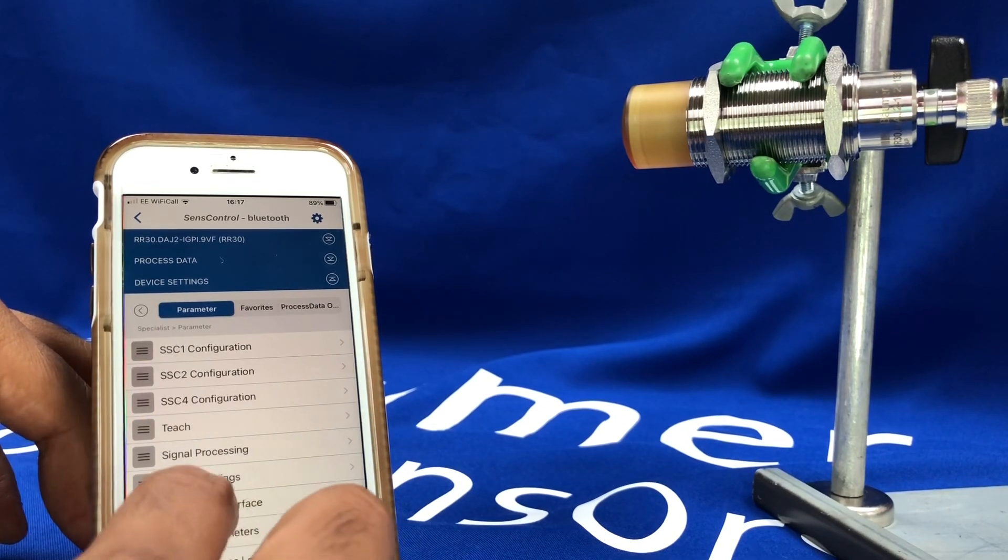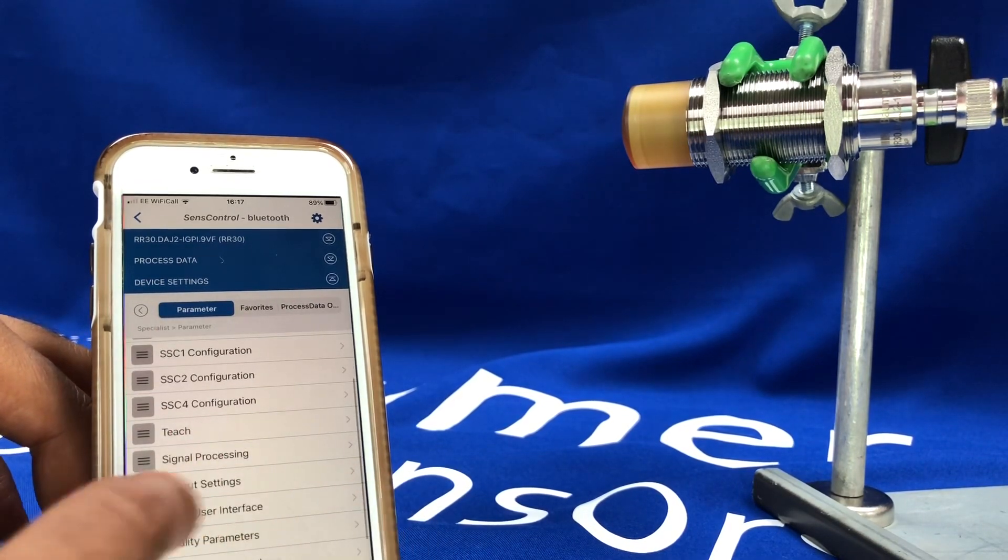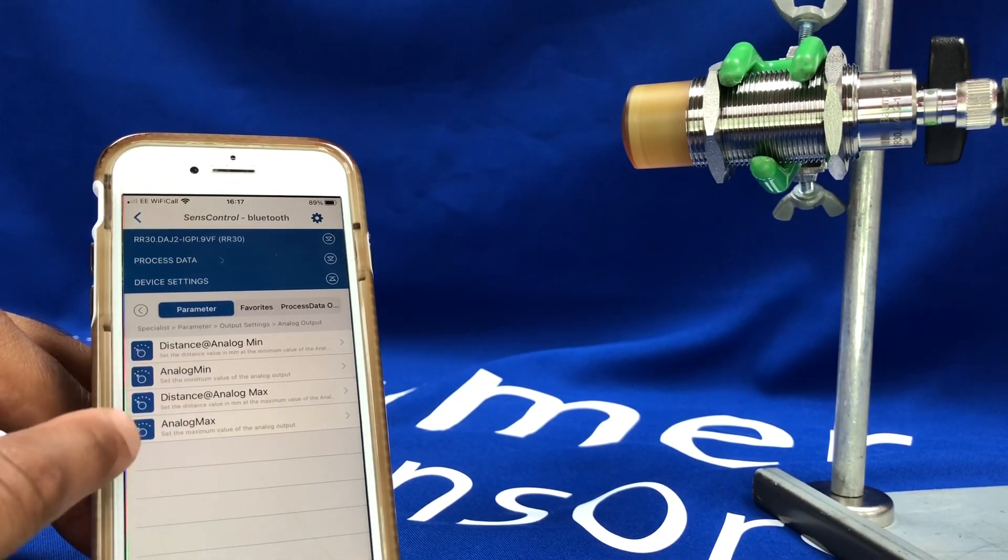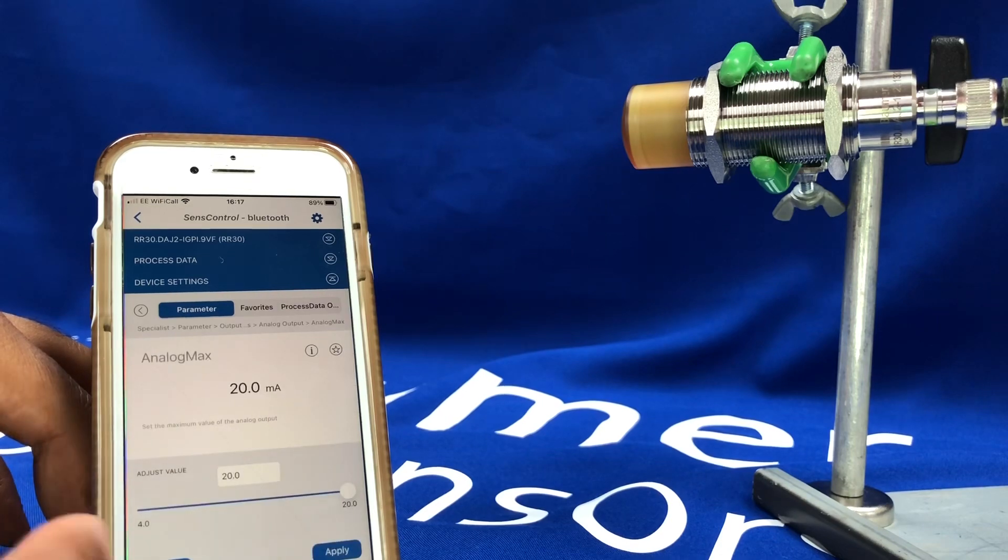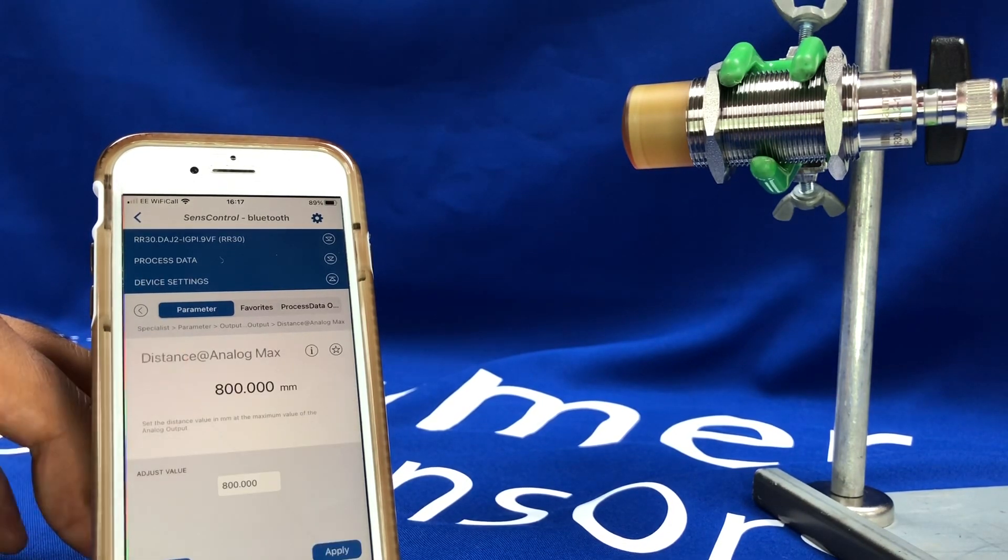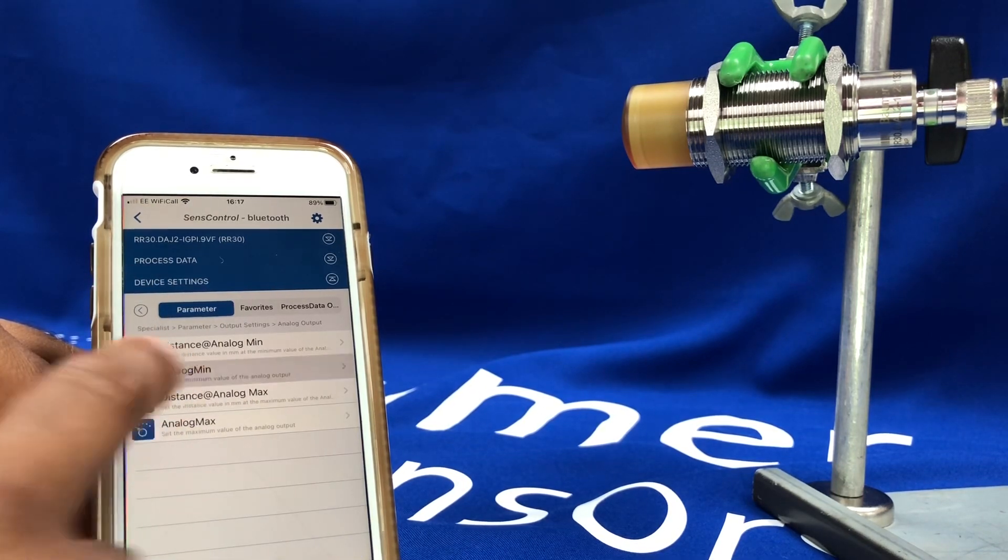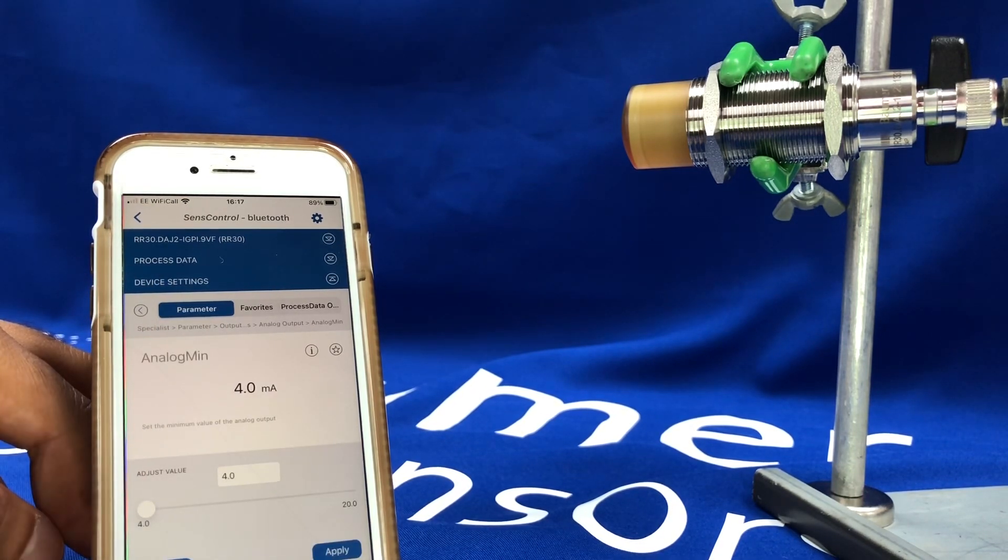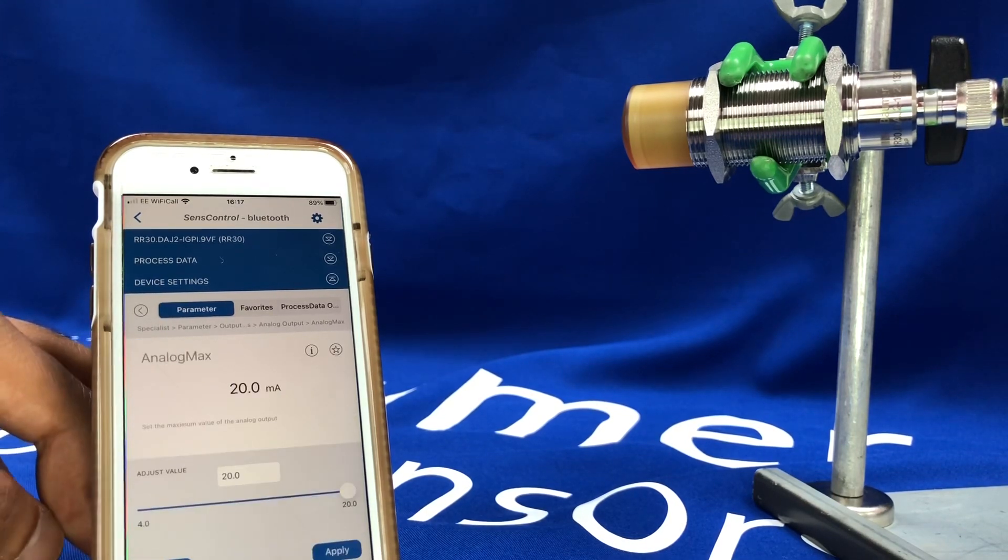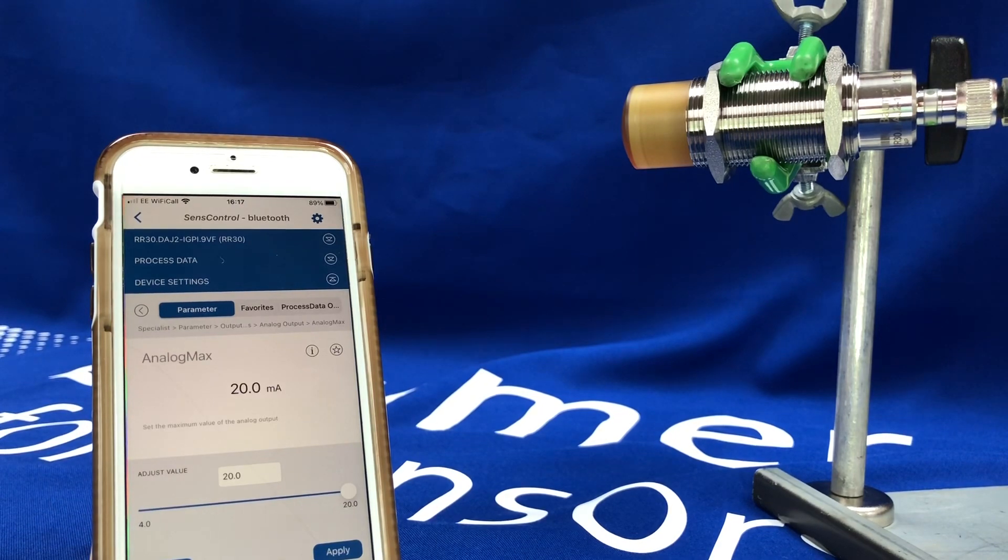In the output settings, you can select the analog output, set the minimum and maximum ranges, and also the milliamp for those. So I set the maximum range at 800mm and the minimum range at 300mm, with the analog minimum at 4mA and maximum 20mA to scale that 300mm to 800mm over.